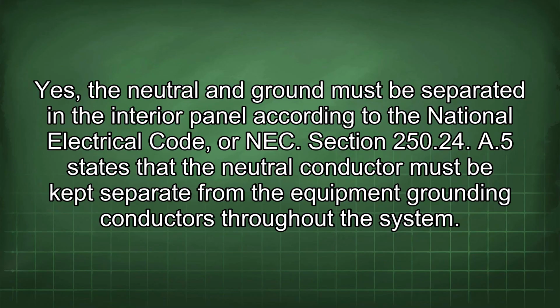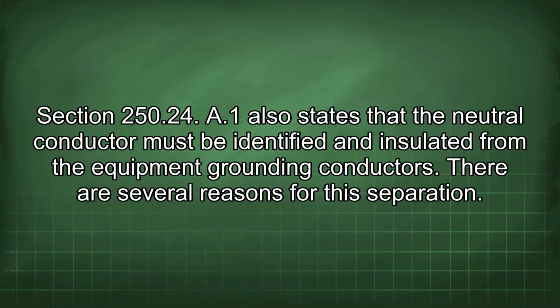Yes, the neutral and ground must be separated in the interior panel according to the National Electrical Code, or NEC. Section 250.24(A)(5) states that the neutral conductor must be kept separate from the equipment grounding conductors throughout the system. Section 250.24(A)(1) also states that the neutral conductor must be identified and insulated from the equipment grounding conductors.